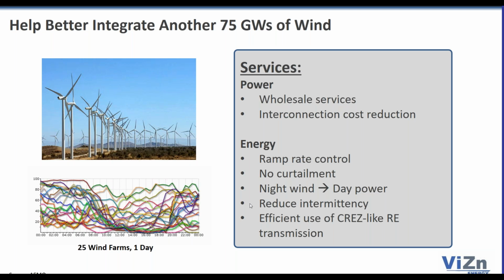What we're starting to see is developers of projects look at their histogram of wind power output over 365 days in a year, or 8,760 hours, and figure out how to oversize the wind farm, add a battery, and minimize the substation size to drive down interconnection costs. It's an interesting analysis. Then the energy services come along: ramp rate control, no curtailment.